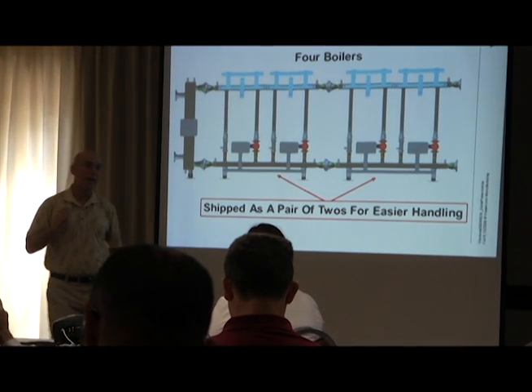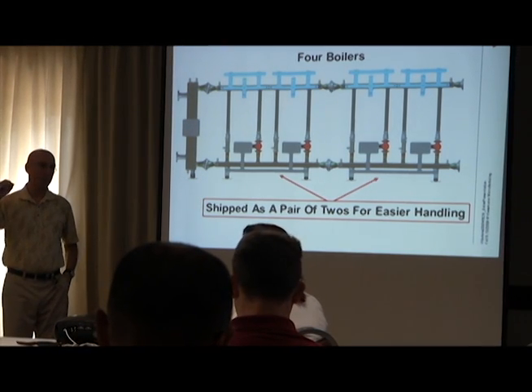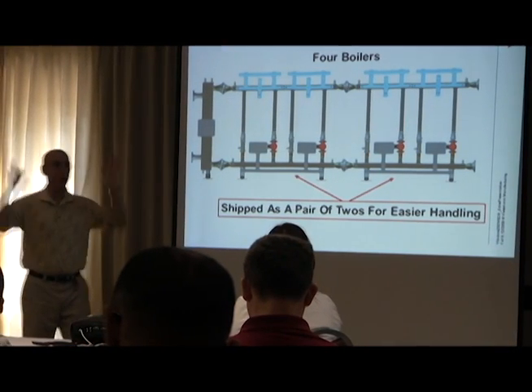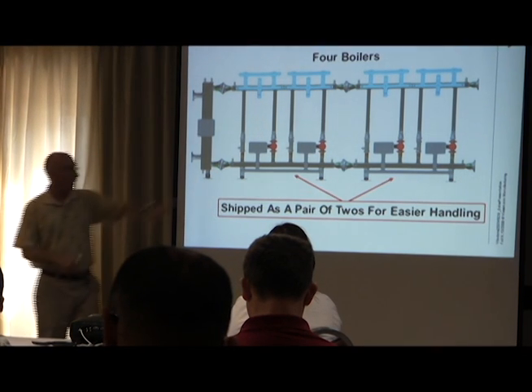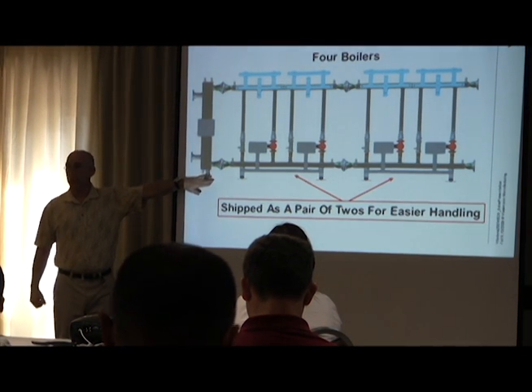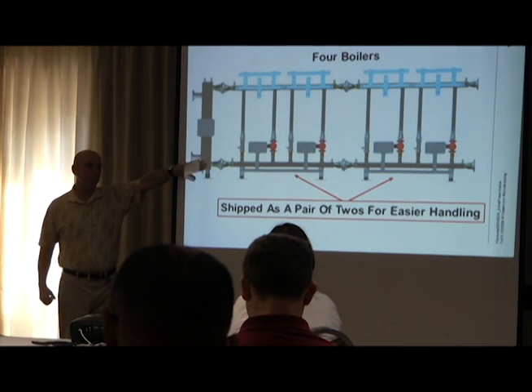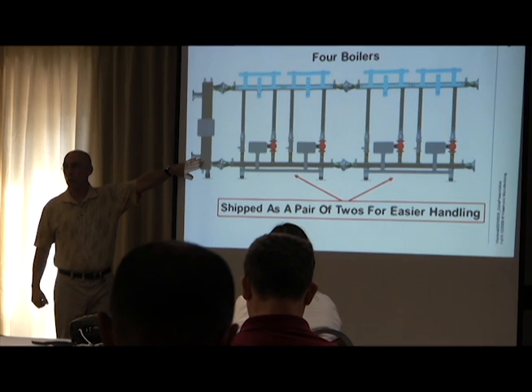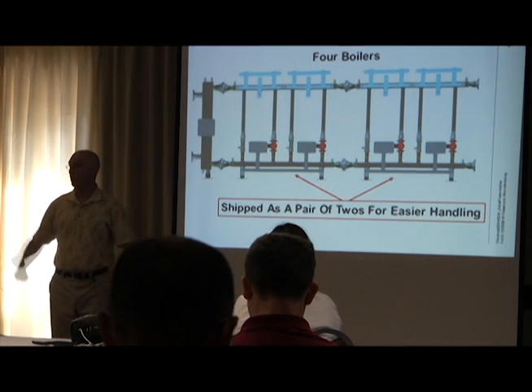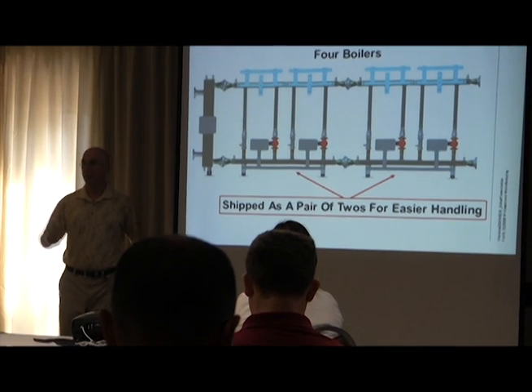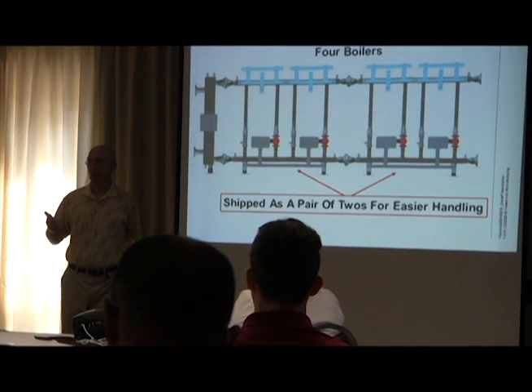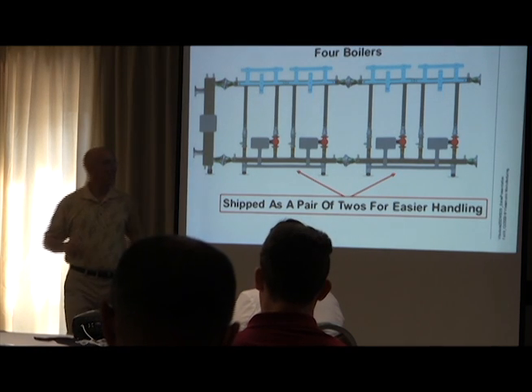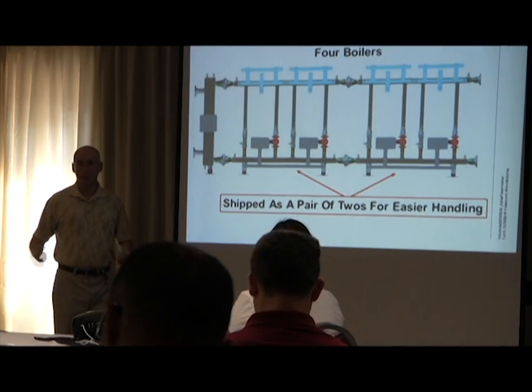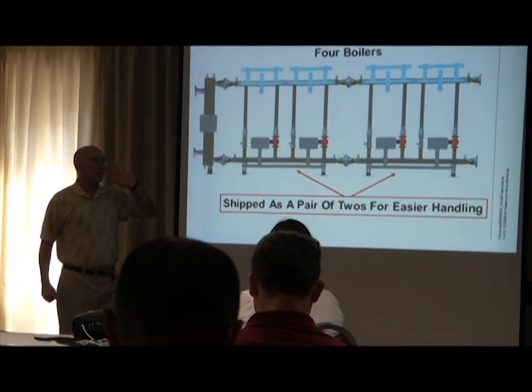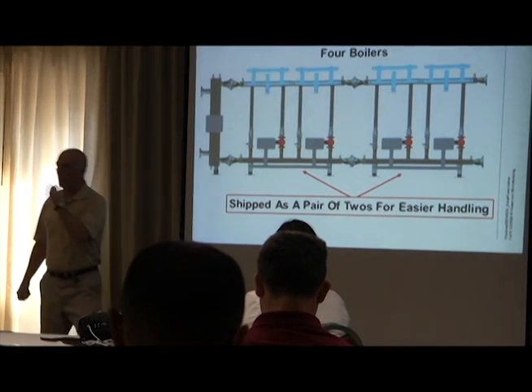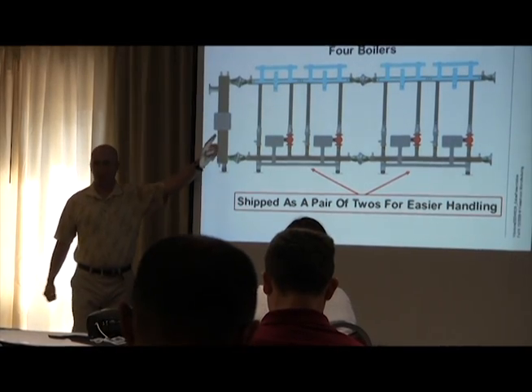It's very, very helpful, especially in a retrofit situation when you have no clue what the flow rates are on the other side. If you're in a new building and you're engineering a new building, then you just basically size that low loss header in relation to what you've calculated the flow rates are for the building. And that's for the engineers out there. Any engineers out there? 1, 2, all right, good. So you could use that for it's like, if you don't know what the flow rates are, put one on.